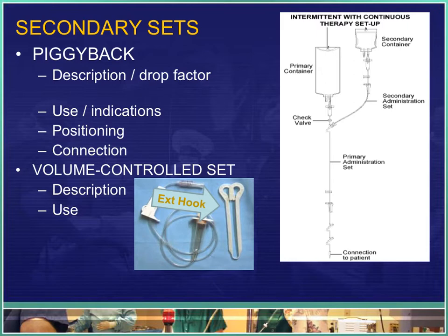They are connected with a needleless adapter into an injection port immediately distal to the back check valve of the primary tubing. In setting up the piggyback set, the primary infusion container is positioned lower than the secondary container using the extension hook provided in the secondary line packaging. As Ohio LPNs authorized to practice limited IV therapy, this is another type of tubing you will be working with when administering antibiotics.